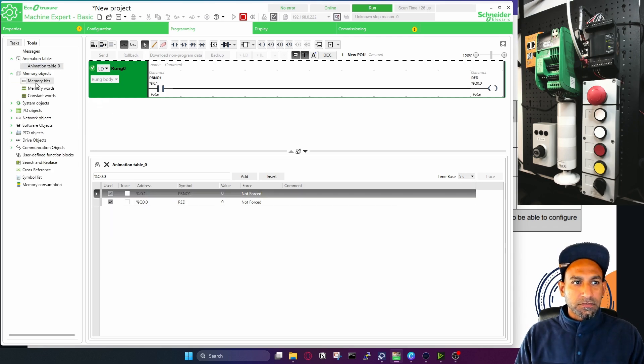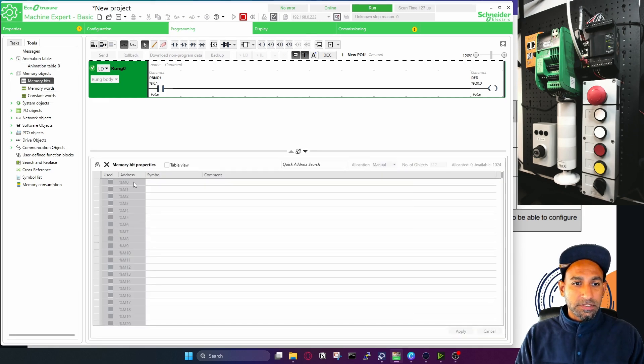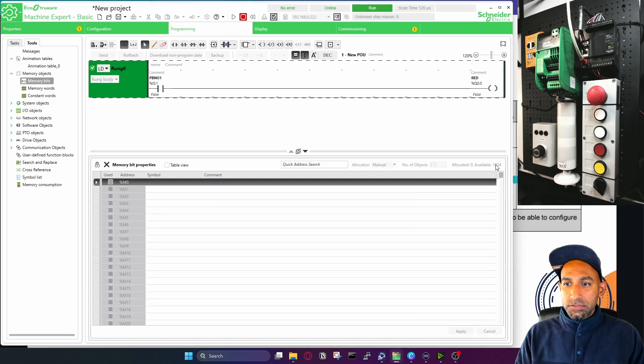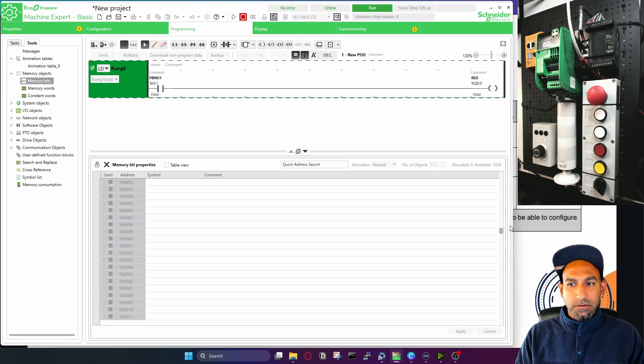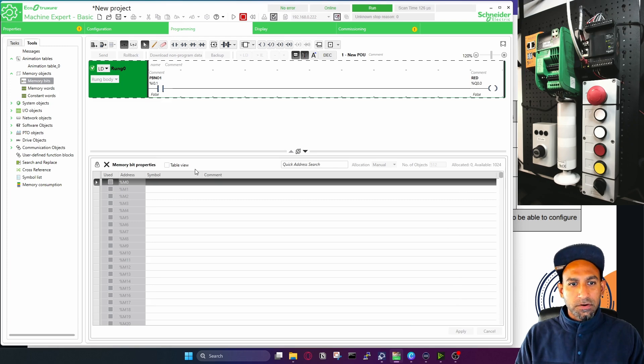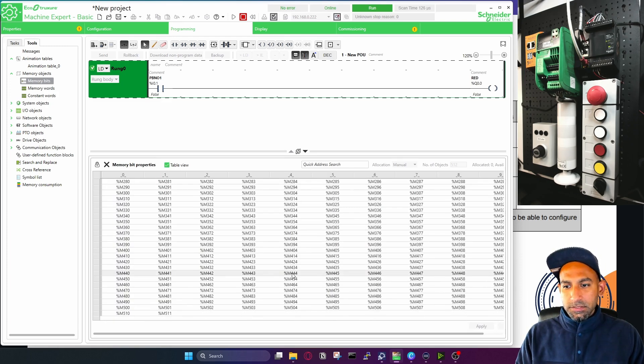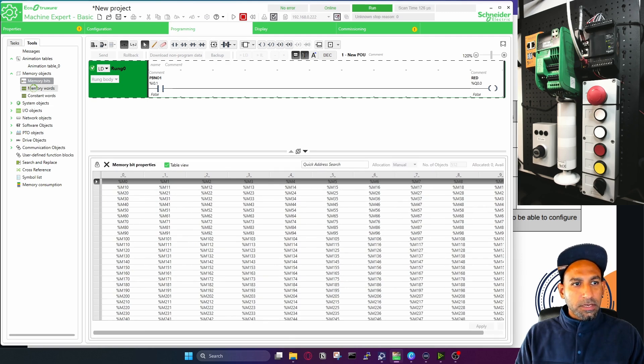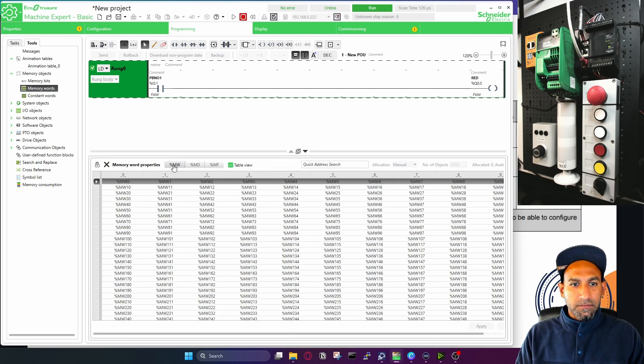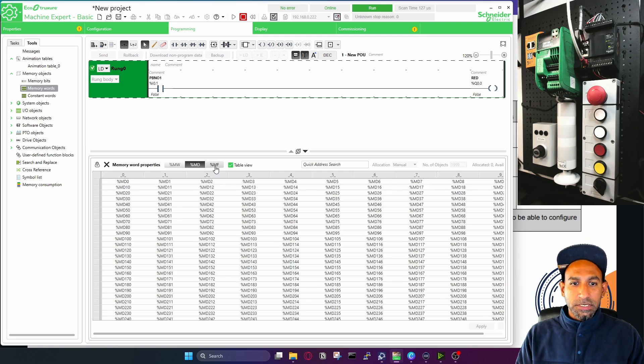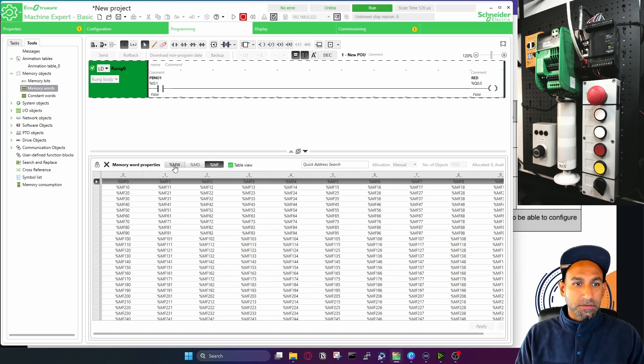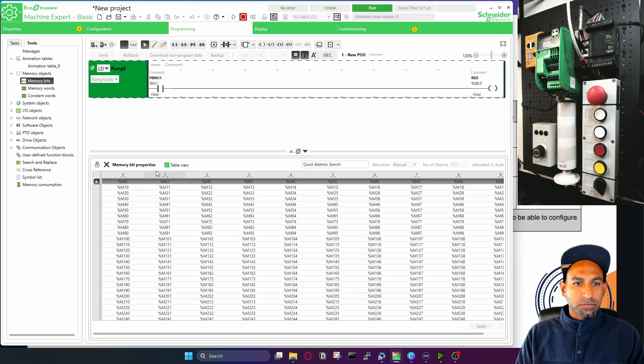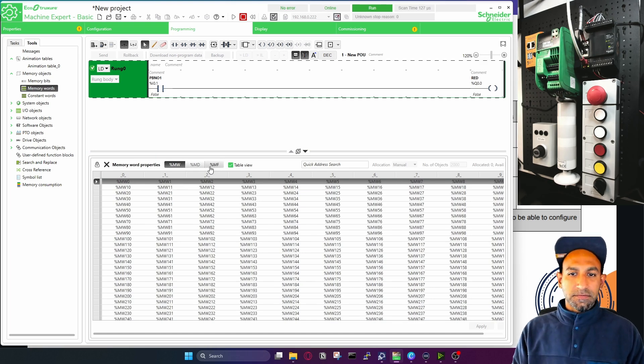Then you have memory objects. If you want to know what memory bits, words, or addressing is available in your PLC program, click on memory bits — memory starts at m0 and goes up to m509 addresses. For memory word, use the prefix mw; for double word, md; and for floating point, mf. If it's just a bit, use m0, m1, m2, and so on.